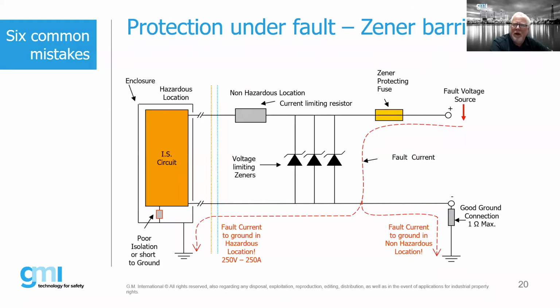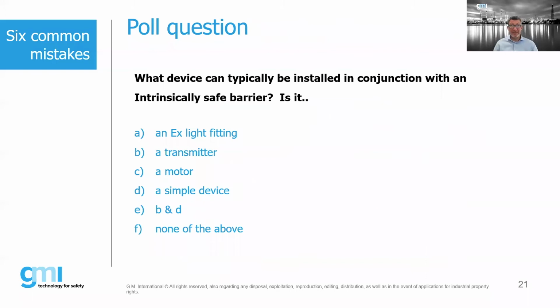Now, here's the issue under a fault condition with Zener barriers. If we do not have a good earth, or we have a disconnected earth, we potentially could be taking an earth fault onto the dirty side, or we don't have good isolation. And so it is very, very critical that when we use Zener barriers, we must have a dedicated IS earth. As we'll talk about with some of the mistakes that we see in the field, this is in many cases one of the biggest issues that we run into when we do inspections: the quality of the earth, or whether or not a dedicated earth is actually there. Sometimes it's actually completely missing.